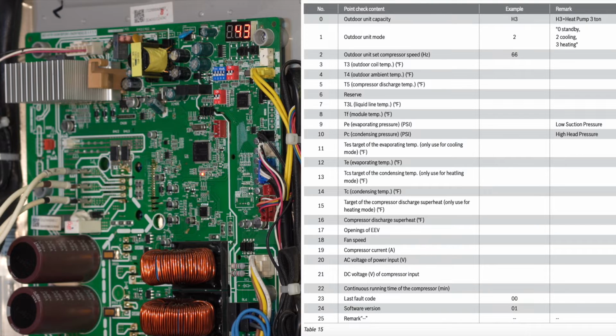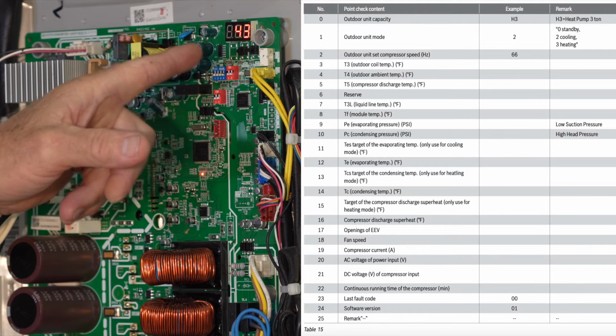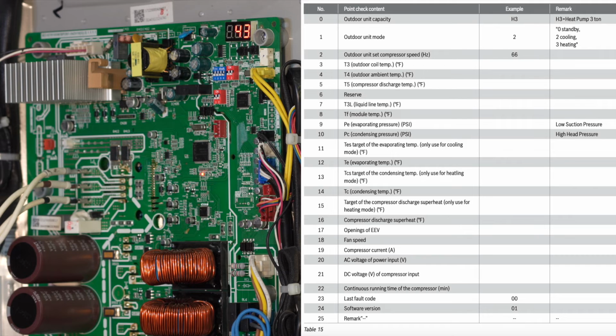So I don't have to have a voltmeter and go between common and yellow to see what's coming into the unit. I could just push a button to 01. And tell what mode we're calling for, correct. Wow. And also when you guys call in on the phone and we're taking technical calls, just keep in mind when we're going through these parameters, we can see together exactly everything that's going on here. Number 2 was the outdoor unit compressor speed. So at that particular time, we were in the forced mode. So we know that our compressor was ramped all the way up. The 2-ton ramped all the way up. It was 45 hertz. So that's 100%. That's 100%. Yep. That's 100% capacity.